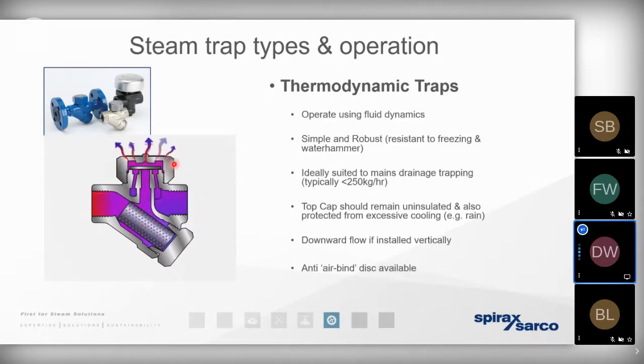And as the flash steam condenses and gives up its energy against the head of the trap, it's going to condense, its volume's going to collapse, it's going to pull a vacuum. So this little disc is rising and falling. So it's allowing the steam pressure to constantly spit out a very small mass of high temperature, high pressure condensate. So if we're ever stood next to this trap in operation, we should hear two things. We should hear the operation of the little disc clacking open and closed, and we should hear quite a violent blast action of the condensate being discharged to waste.